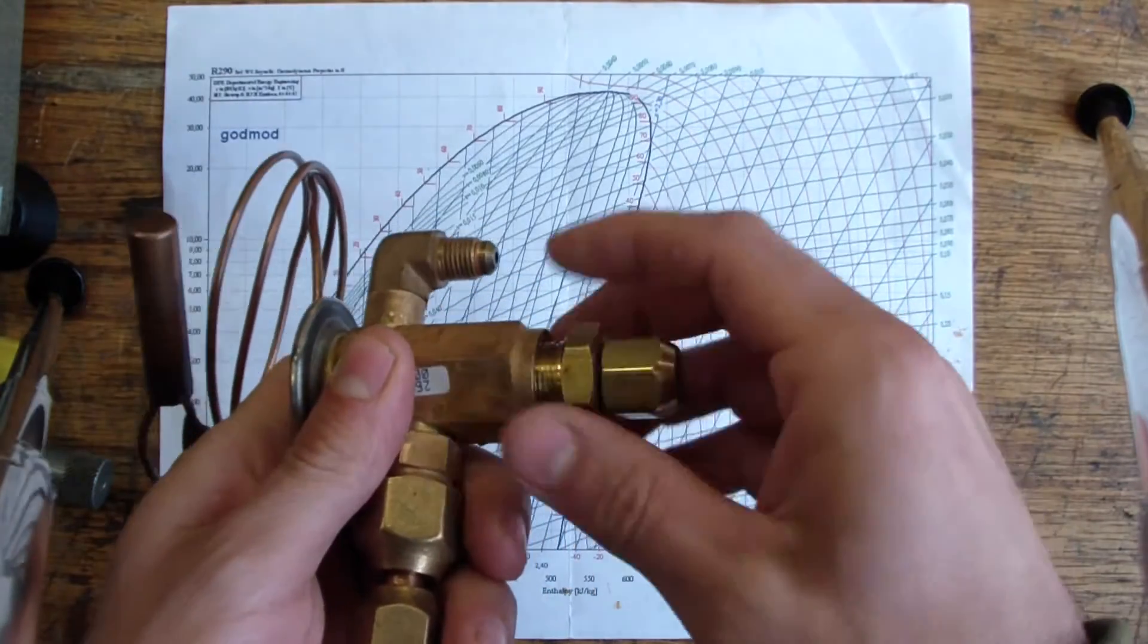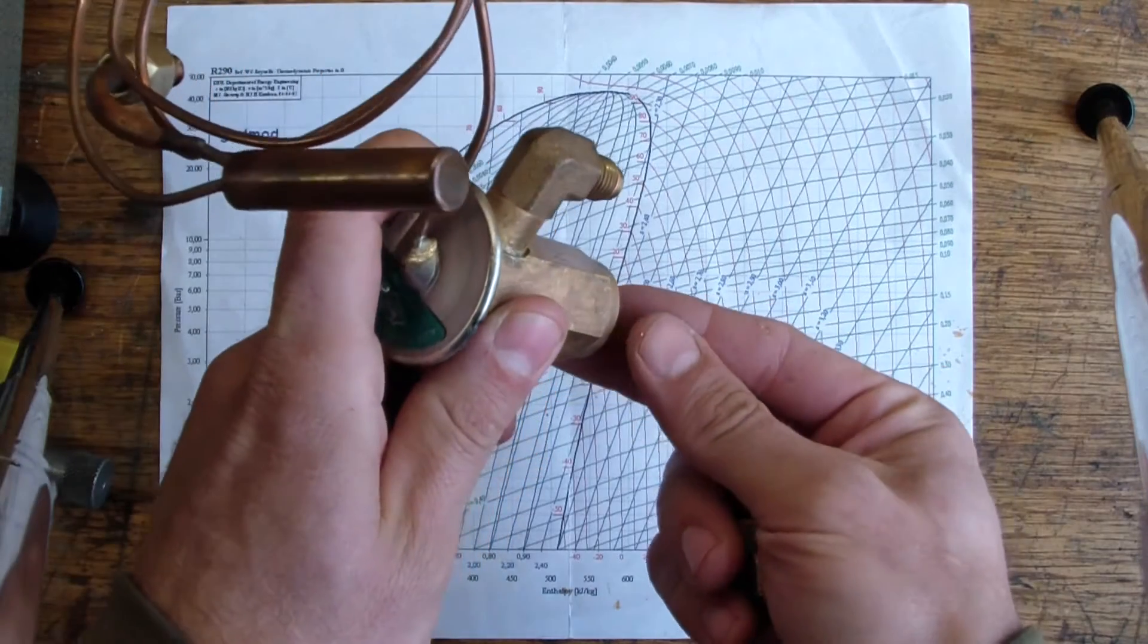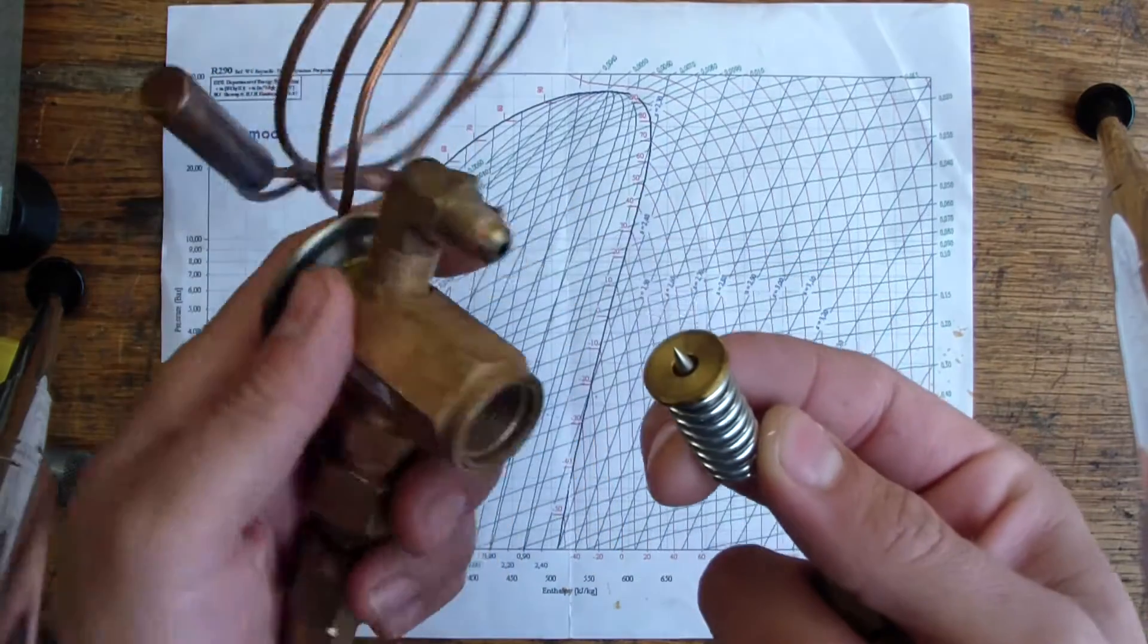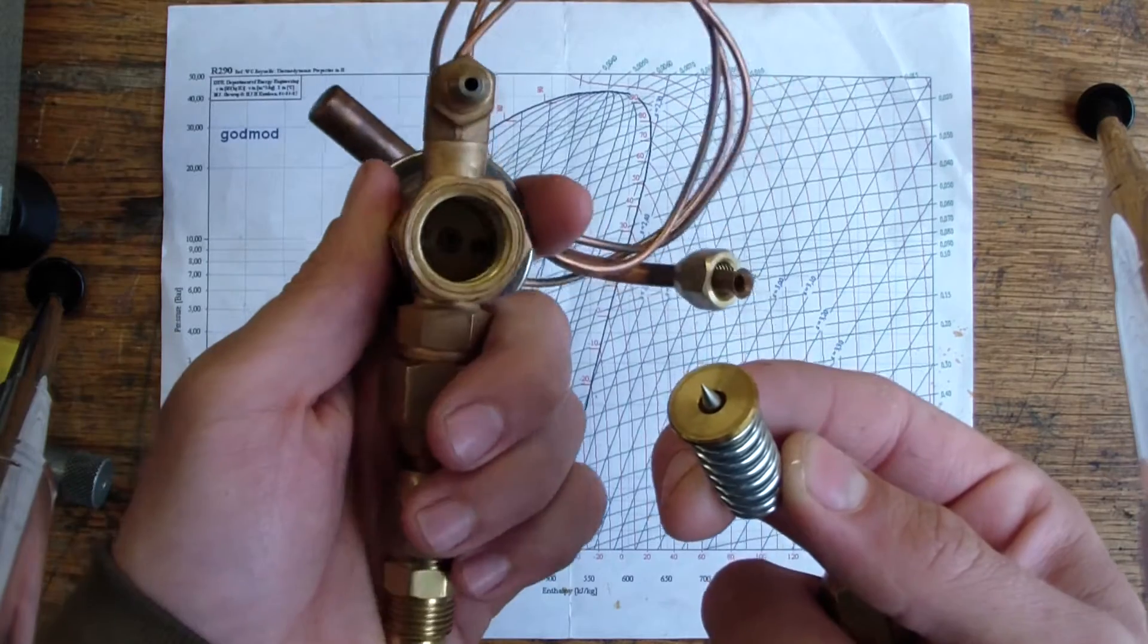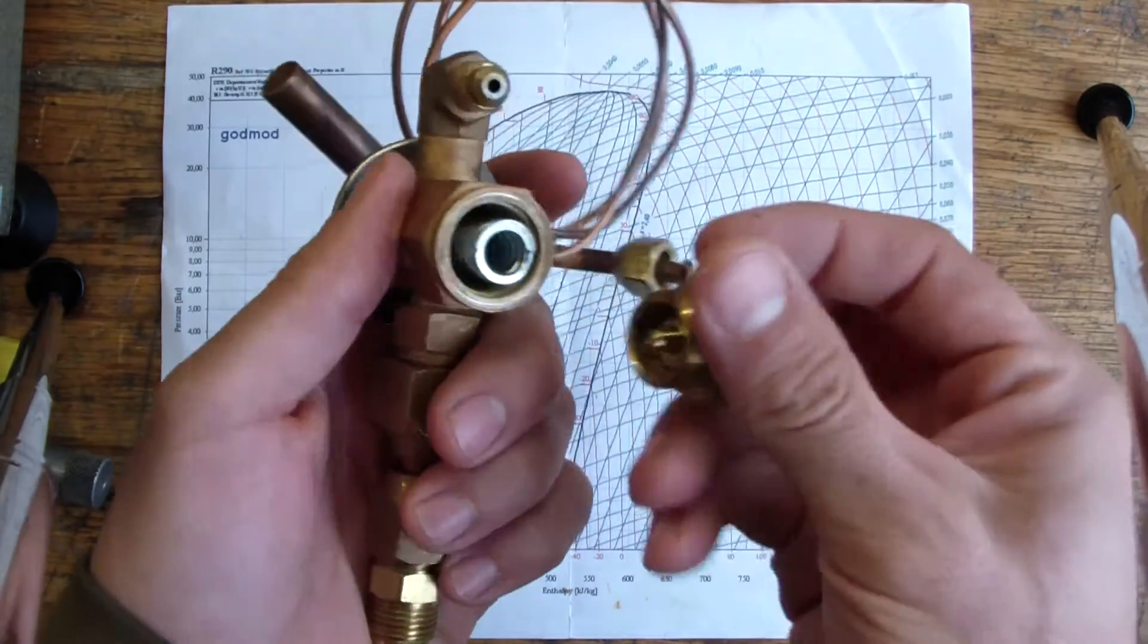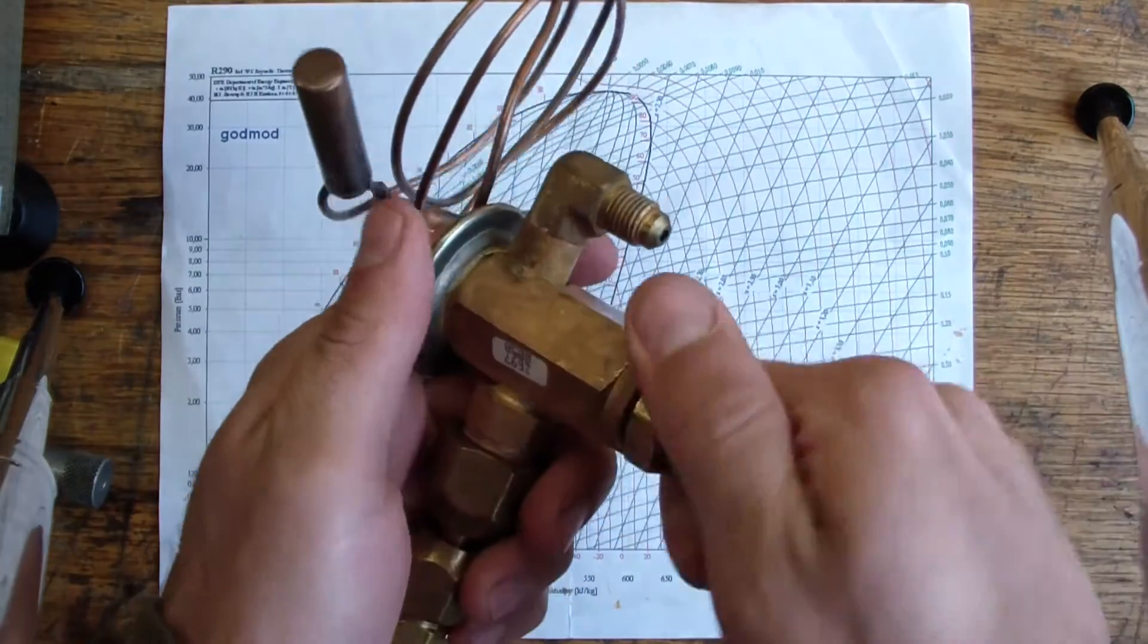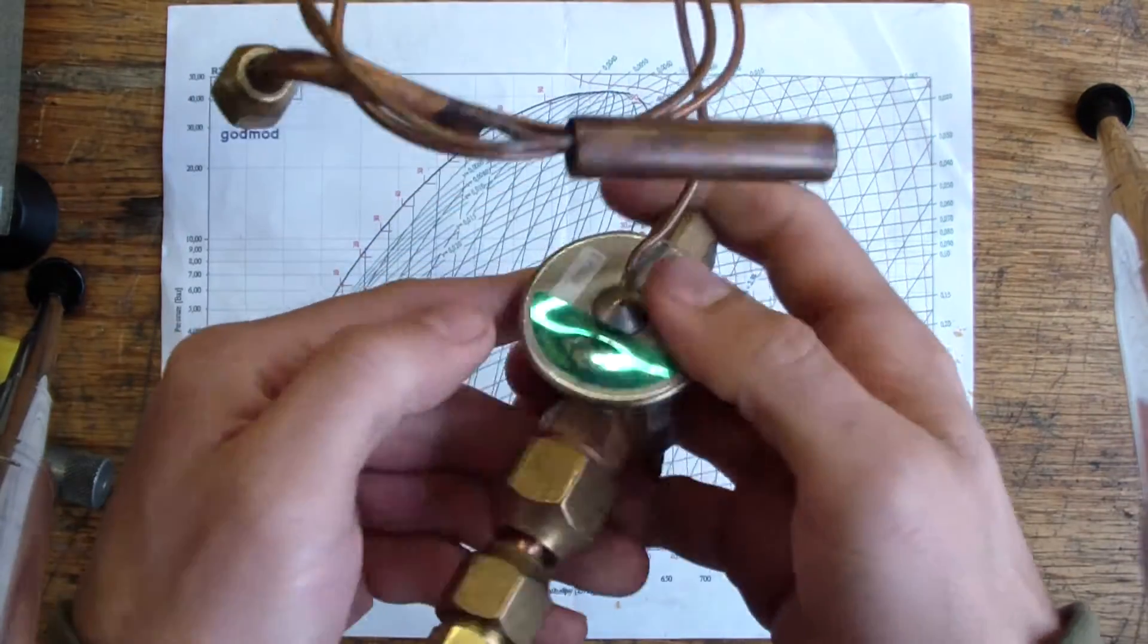Take the bottom off of this. It's not hand tight. I just loosened it previously. And there you can see the fine point of the needle. And it's got a kind of a mating surface, a hole in the bottom there. There's also two pins in there. See this whole assembly goes together. When you tighten this up, there's pressure put on that spring, which holds the needle up against the valve seat. There's a diaphragm here.